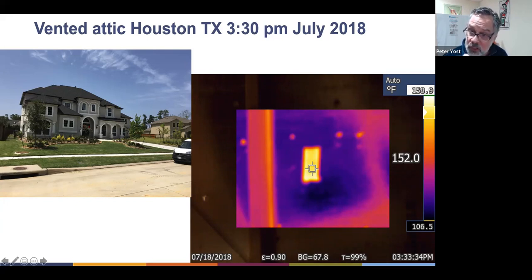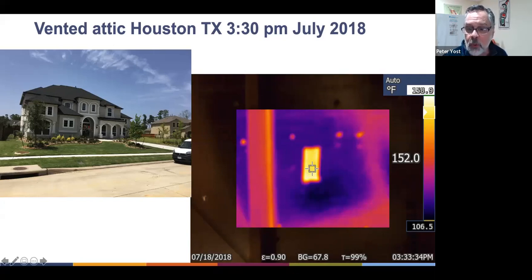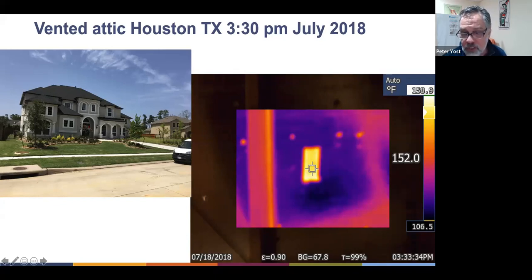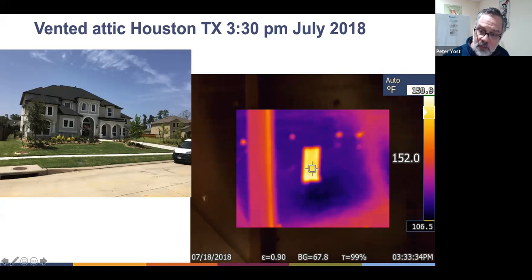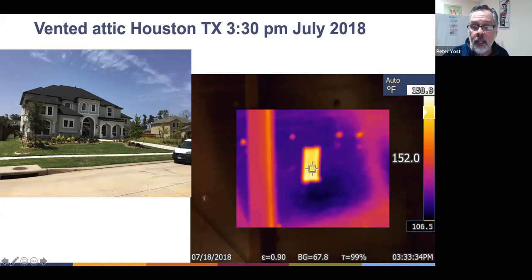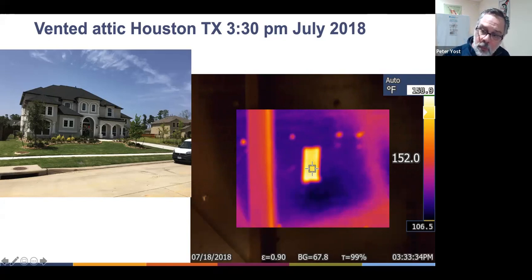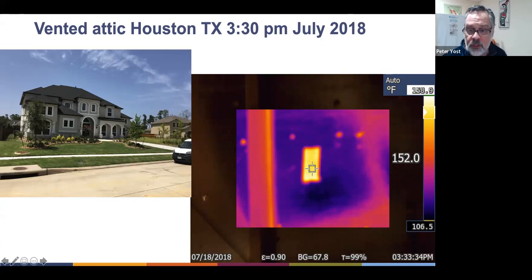Down at the bottom of the image, you can see epsilon 0.9 — that means I've set the emissivity for the surface I'm reading. This is interesting: if I'm trying to read a radiant barrier with an emissivity of about 0.05, why would I choose 0.9? It's because I was targeting what was in the crosshairs, and I knew the emissivity of that spot was actually 0.9. The background temperature was set incorrectly — I had it set for the conditioned space below and forgot to change it when I went into the attic. It should be at 100°F.